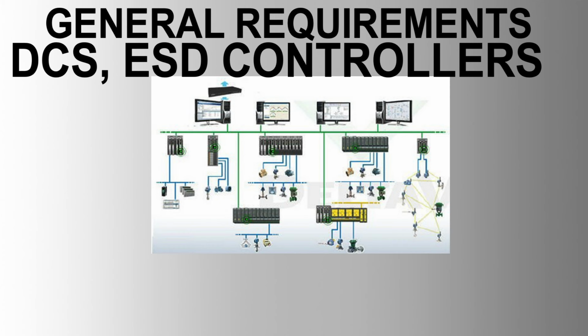10. Data communication and redundancy. Redundant data highways. 2 data highways active at all times with capability for single highway operation without degradation. Communication diagnostics for continuous monitoring and failure alarms. Redundant bus or continuous loop design to prevent single point of failure.